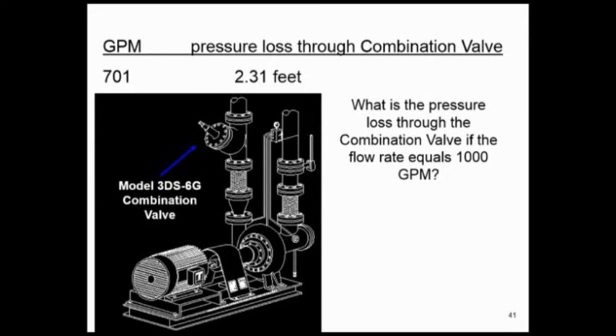And I like to add this to the conversation without calling anybody. You should be able to do this. You should be able to take the little formula I taught you a few minutes ago and say, wait a minute, what do I know? I know the pressure drop at 701 GPM is 2.31 feet. What would be the pressure drop at 1,000 GPM? From that square relationship, that's all we're asking you to do.